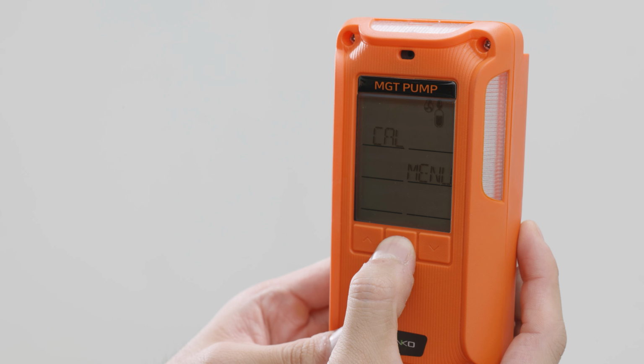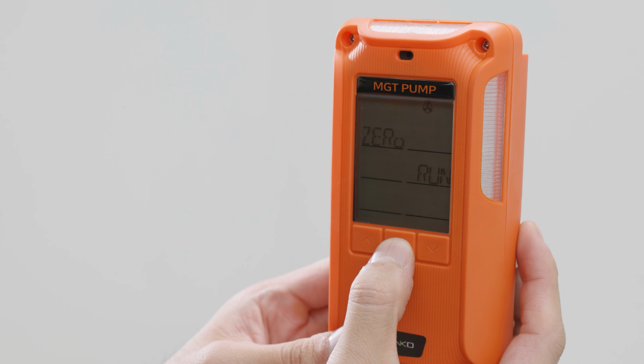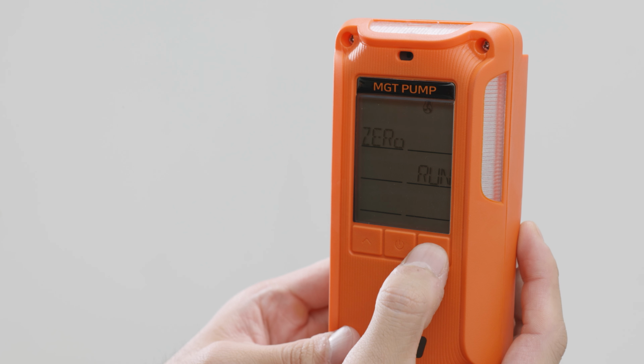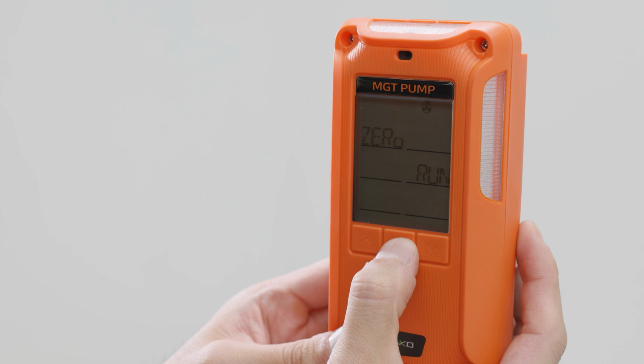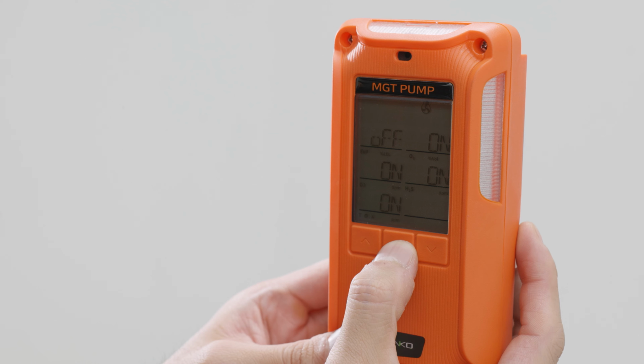Next, return to the initial setting mode and press the Down button to enter the next menu, the Cal menu. Within the Cal menu, there are 3 calibration options: Zero Run, Span Run, and Pump Run. Zero Run is a fresh air calibration performed in an ambient atmospheric environment.